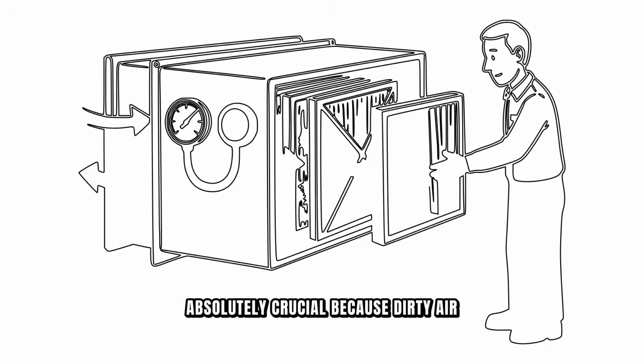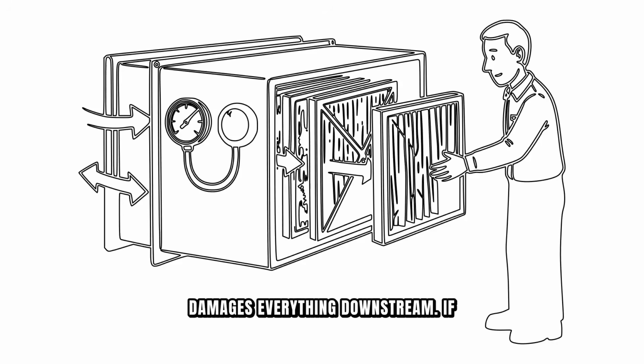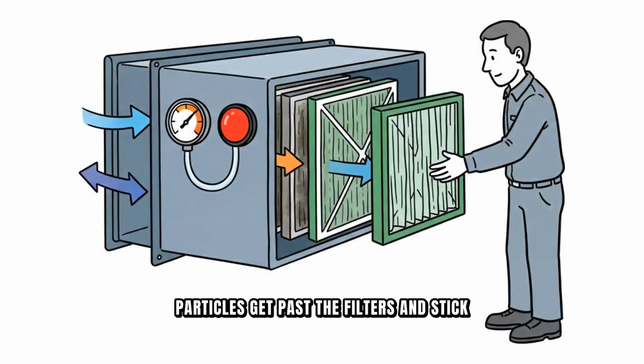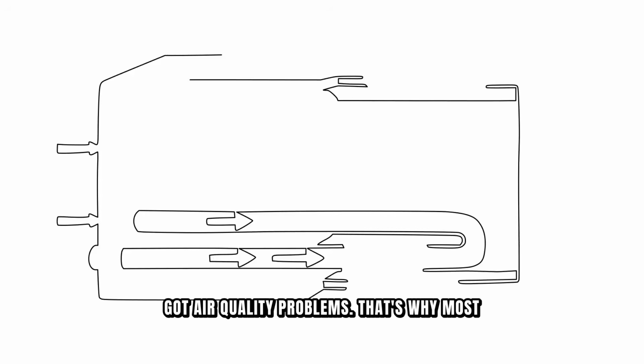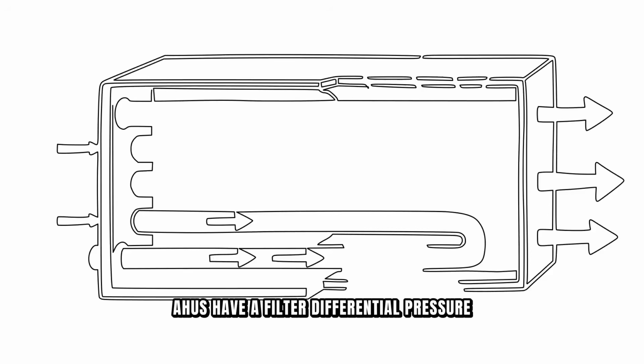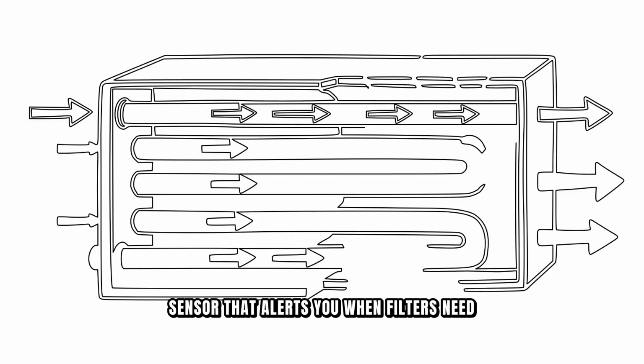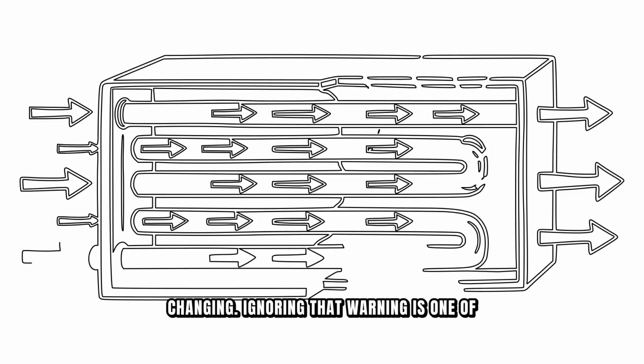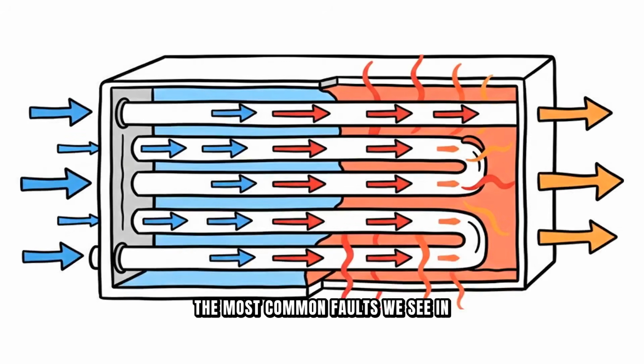These filters are absolutely crucial because dirty air damages everything downstream. If particles get past the filters and stick to the cooling coil, you lose efficiency. If they circulate back into the building, you've got air quality problems. That's why most AHUs have a filter differential pressure sensor that alerts you when filters need changing. Ignoring that warning is one of the most common faults we see in the field.